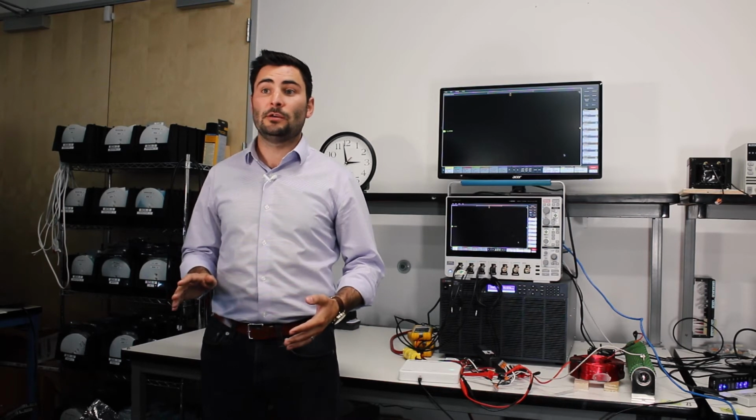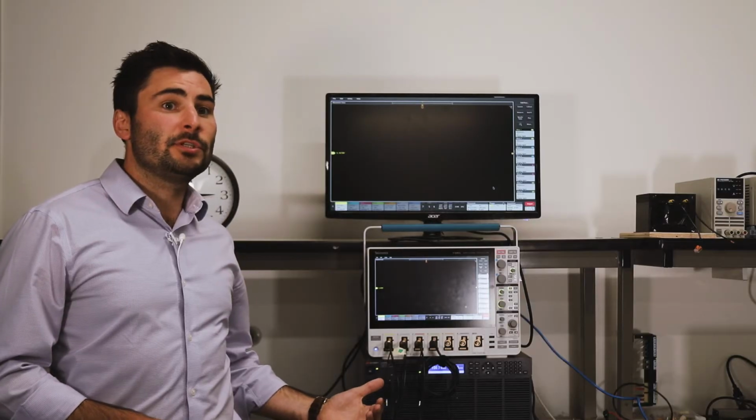Electromechanical circuit breakers have galvanic isolation, which provides more protection than the dielectric isolation that solid-state switches have. Traditionally, solid-state switches could never handle this voltage spike, which can easily hit thousands of volts, with the dielectric strength alone, until Amber. Amber's demo behind me can recognize the voltage spike through extremely fast sampling and can nearly instantaneously cap this spike through switching before the voltage is able to get too high, causing a catastrophic failure. Without Amber, a solid-state device would fail if subjected to the same conditions as this test.